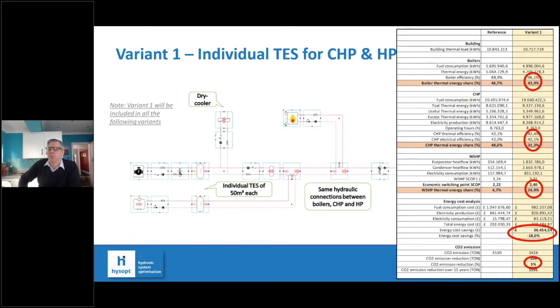It doesn't really change the boiler share so much. What ends up happening is we get the heat pump to run more often, which is great from a carbon point of view, but that's at the detriment of the CHP engine. So it has a positive impact for CO2, but a detrimental impact on the overall annual energy costs - energy costs go up by about £18,000 a year, and the CO2 goes down by about 3%.